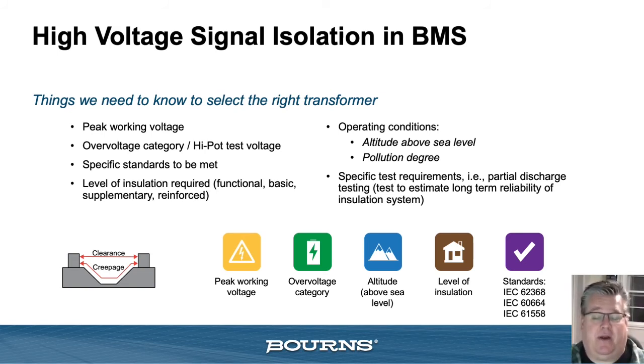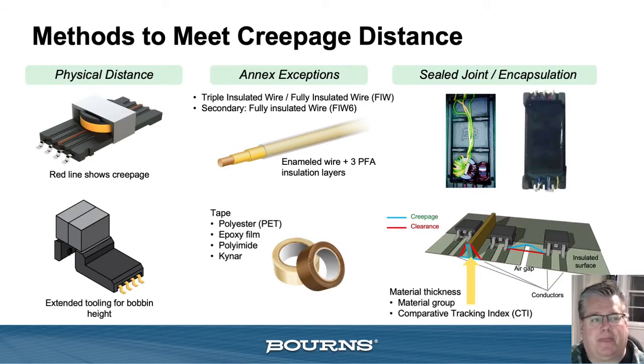Then there are any extra operating conditions you might have, regardless of other criteria that you have for safety. Does it have to operate so many meters above sea level? What's the pollution degree, or the dirtiness of the environment that the transformer is going to operate in? And then any other specific tests that you may need: partial discharge, or reliability or environmental testing that needs to happen as well.